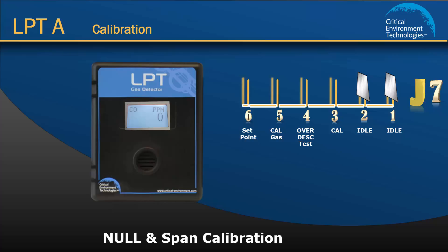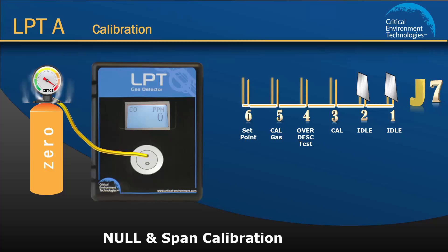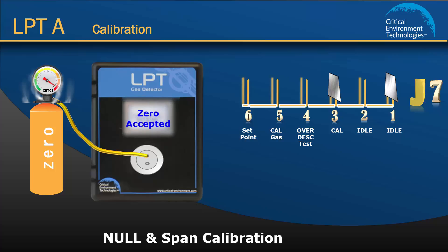To begin the null calibration, attach the regulator to the cylinder, insert the calibration adapter into the sensor opening in the front of the enclosure door and open the regulator valve fully allowing the zero gas to flow over the sensor. Move one jumper from the idle position to the cal position. The display will show calibration waiting to zero. If the reading is accepted, the message zero accepted will display and you can continue with the span gas calibration.